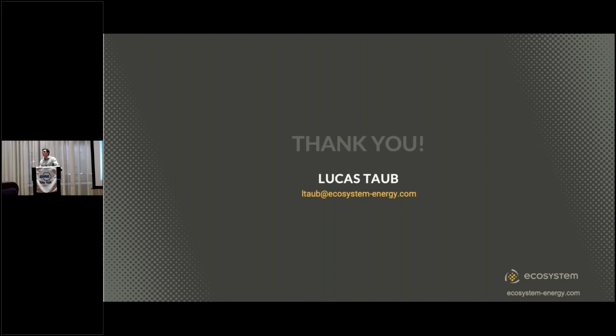In the context of this, I don't have a great answer for that as of now, but if you come talk to me afterwards, we can talk a little bit more about it. But there are limitations to that. The way that I would approach it is you would design your system from the top down. If you have your air source heat pump on the roof, you can supply up to a lower floor, and then you have a separate system that would cover the lower floors, potentially either a second air source heat pump system, or you capitalize on more of a distributed air source heat pump where each unit would have its own heat pump. So it's not fully addressing how you use a heat pump to cover the full building, but it's a way that you can leverage a different system that still achieves the same goal.